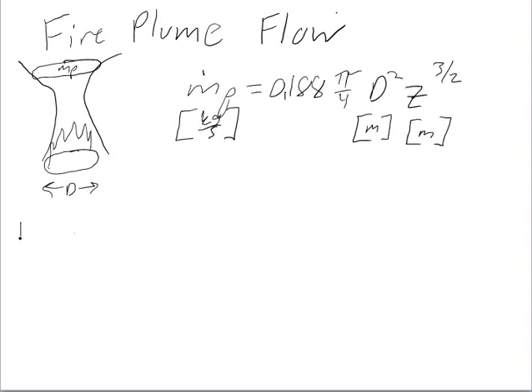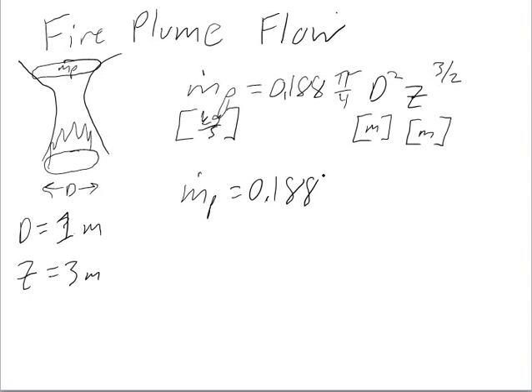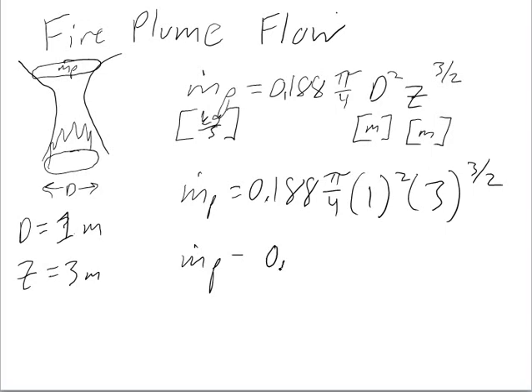So let's say we had d is equal to 1 meter, a 1 meter diameter fire, and we were interested at what the plume flow was at 3 meters above the floor. So we would go m.p is equal to 0.188 times pi over 4 times 1 squared times 3 to the 3 halves power. And then m.p is equal to 0.767 kilograms per second.